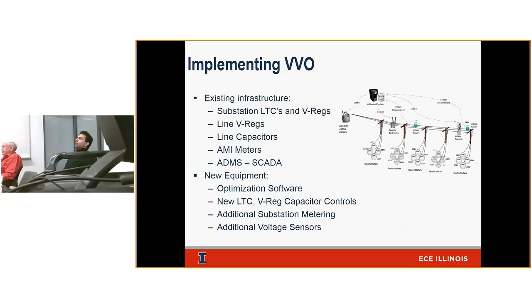A big component for that is AMI — Advanced Meter Infrastructure. Those are meters at the customer premise that typically bring back KW and KWH information for billing, but many also have the capability of bringing back voltage, current, temperature, and all kinds of information useful for programs like this. At Ameren, our voltage optimization program uses AMI as a core component. Every 15 minutes, we ping customer meters to find out what the voltage is, feed that back into a central algorithm that decides whether voltage can be reduced, and then sends new settings to all voltage regulators and cap banks.